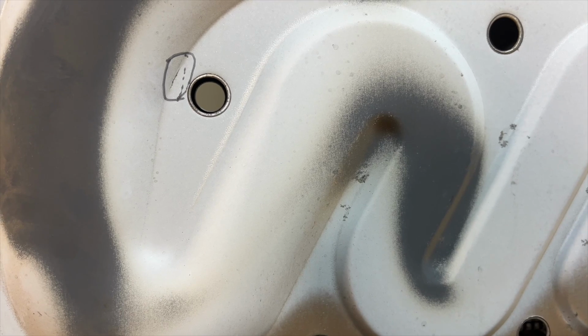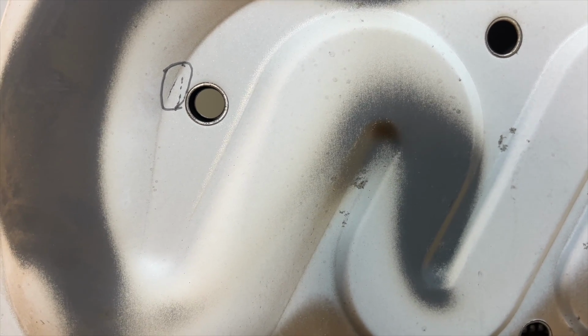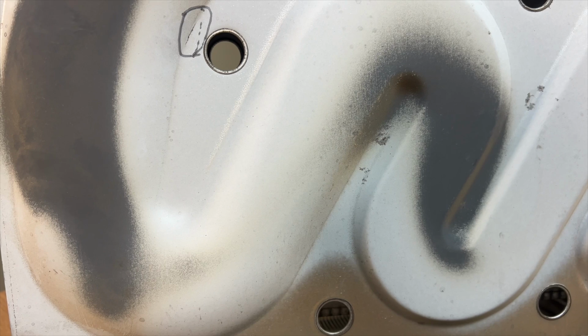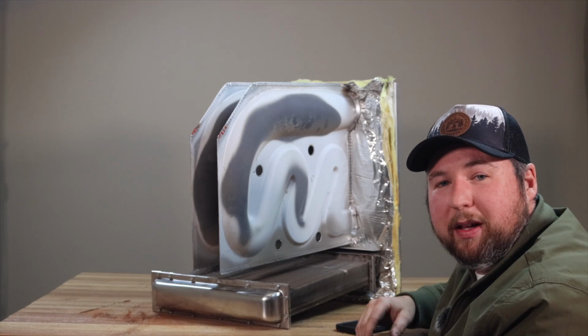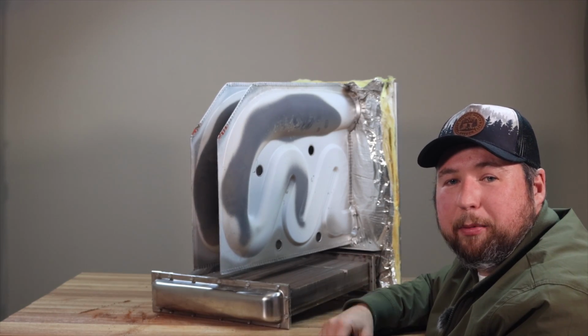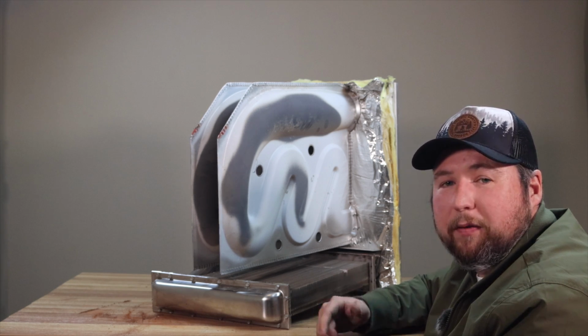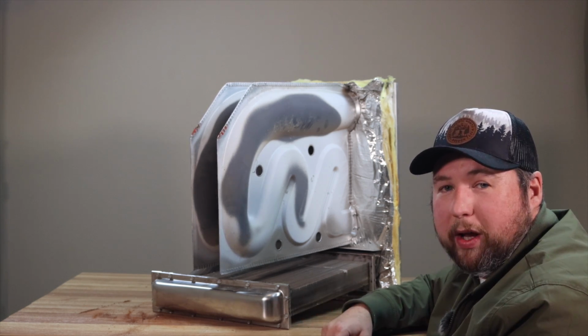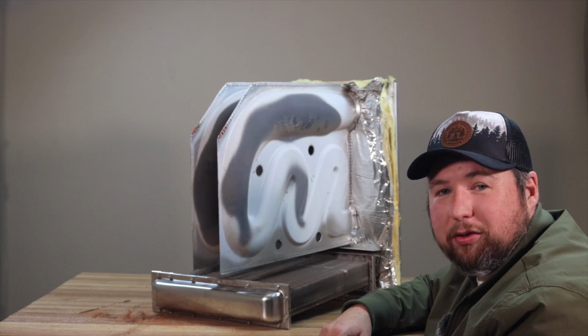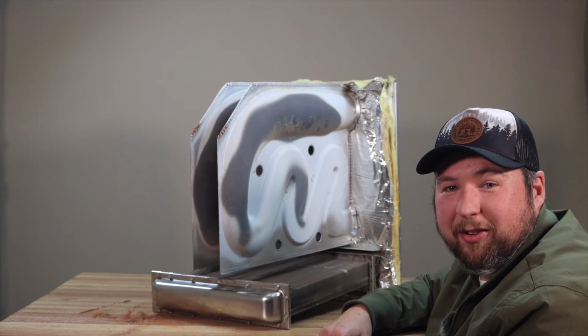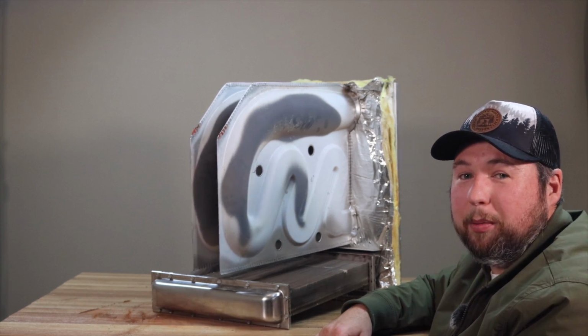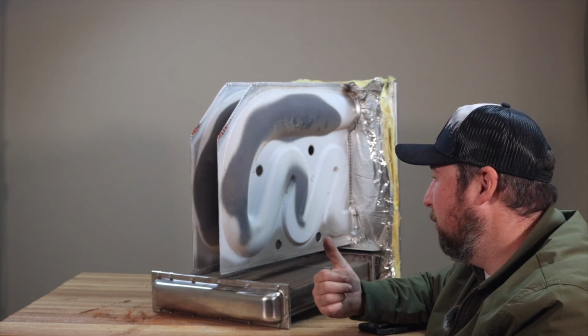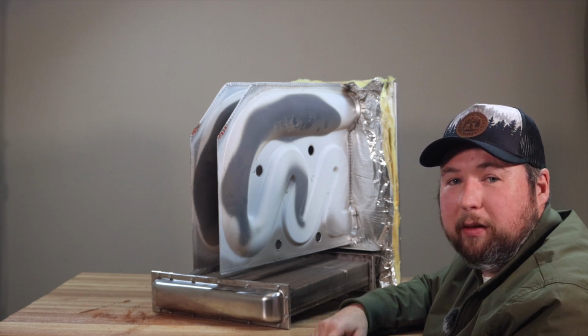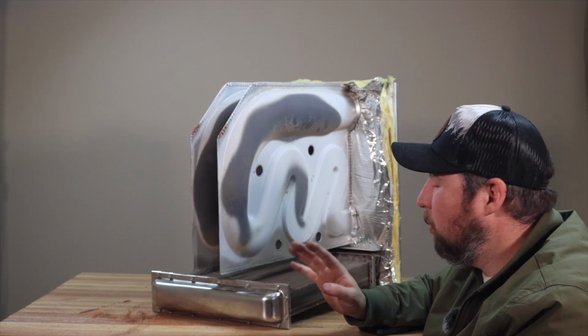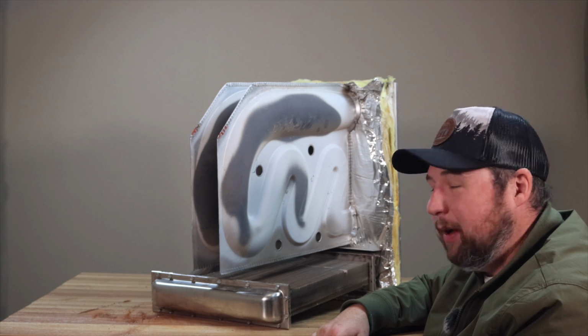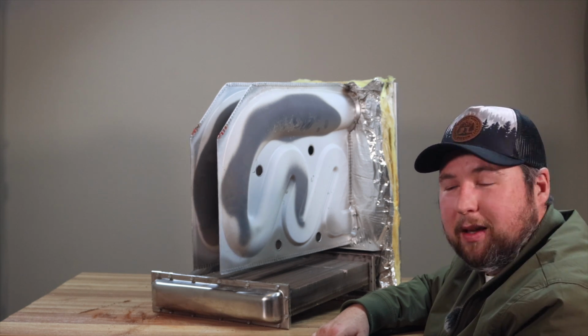And you could tell your customer, hey, your gas pressure is high, or if you notice the filter is really dirty, there's a chance that they don't change their filters regularly. That usually means that they're going to have a lot of temperature stress. Another thing too is if you have a small return, like your return's way too small for the unit, so you have like a 14-inch grill and it's like a 150,000 BTU furnace, you're probably gonna find a crack or major temperature stress. So you want to consider those things as well. But that's what we're doing. We're doing a safety inspection of the furnace, and the best way to do it is to pull the thing out and look at it.